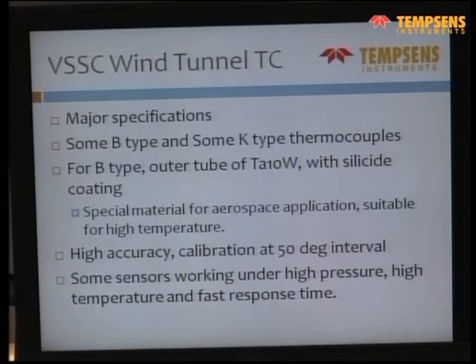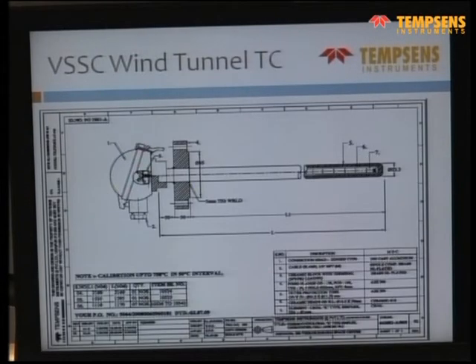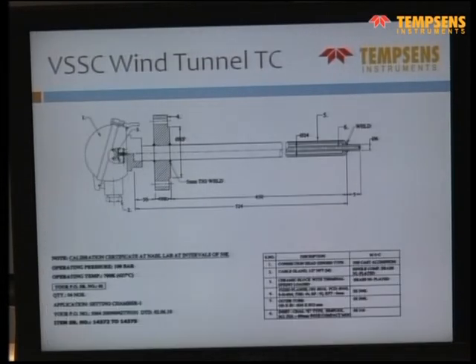So they use what's called a wind tunnel, and we made the thermowells with tantalum, tungsten, and a special coating of silicide. They were calibrated at 50-degree intervals, and they were working in high pressure and high temperature and wanted fast response time. So this is typical for the B-type thermocouple, the drawing, and this one is for K-type up to I think 1000 degree Celsius or so, 700 degree Celsius, and for fast response time we had taken the tip out of the thermowell so that it can give fast response time.